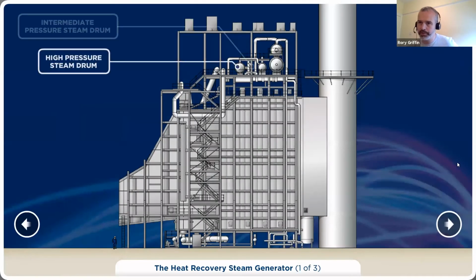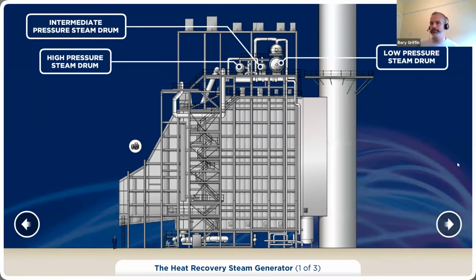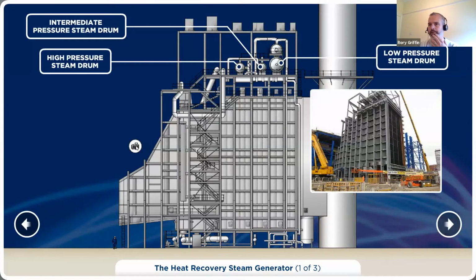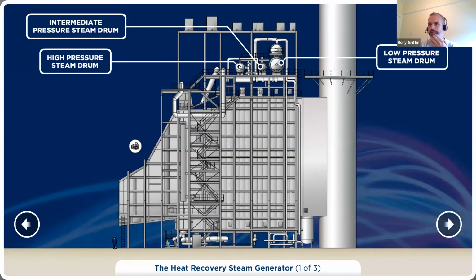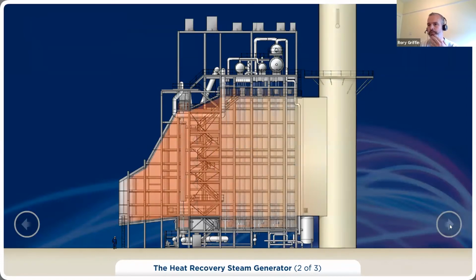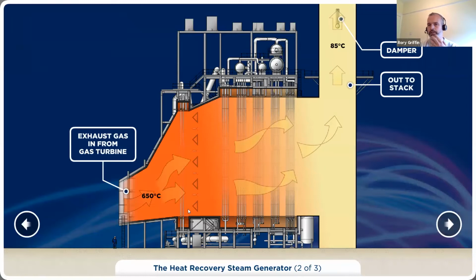So this is basically a giant kettle. It's a boiler, but they call it the HRSG, which is the heat recovery steam generator. So the boiler at Whitegate is quite big. It's probably 40 to 50 meters high, up to the drum level up here. So we'll just get this animation working here. So the exhaust gases come out of the gas turbine. Bear in mind, as it's running, this is almost like a hot tornado.